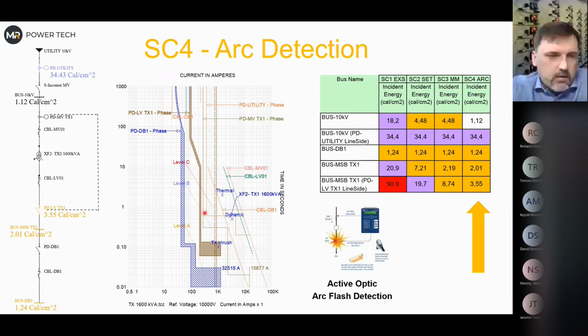So you see, I revert back to the settings we had before in scenario 2, but now we have a separate system that is monitoring everything and is tripping also the medium voltage system. And you don't see it again, but I also did the same for the utility breaker to protect this one. So that's why I see 1.12. The difference now is again that we compare it with scenario 2. So instead of 7, we have 2 calories, and instead of 19, we have 3.55. So that's the difference on the breaker itself.